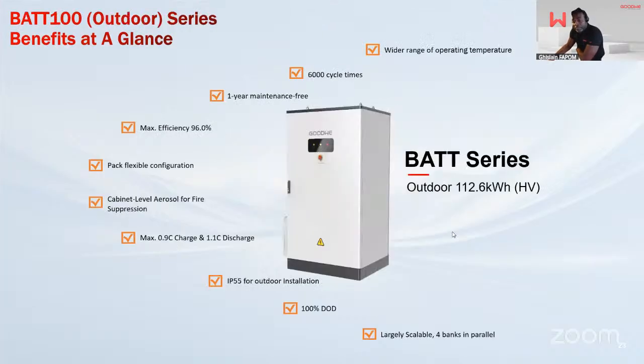Now, the native battery for the ET50 is what we call the BATT100. Only one size for price positioning in the UK. The size is 112.6 kilowatt hours. It's a 1C rated battery. But because the inverter connected to it today is a 50 kilowatt inverter, it will be working today at 0.5C. But the next generation of the hybrid inverter will be the ET100, allowing the battery to work to its full potential of 0.9C charge and 1.1C discharge.